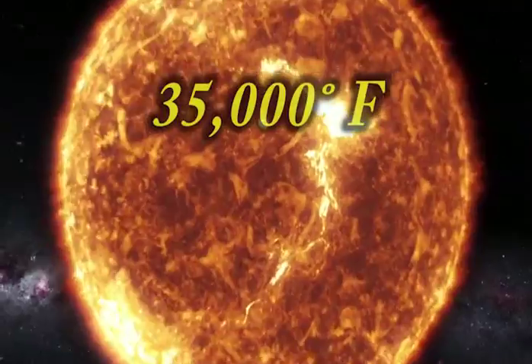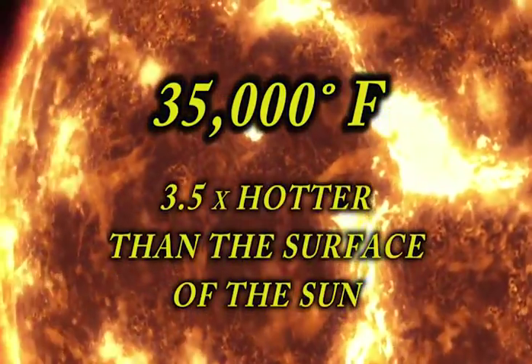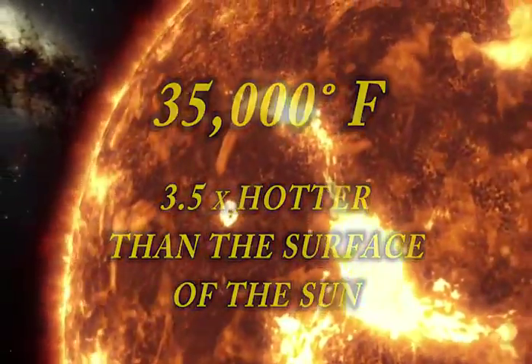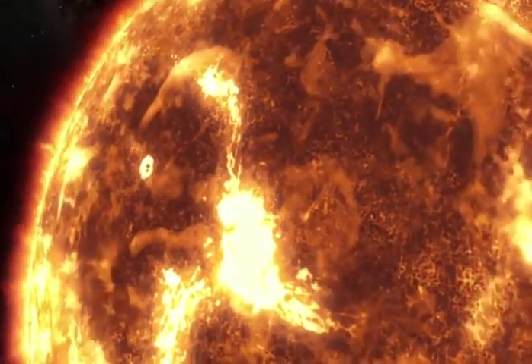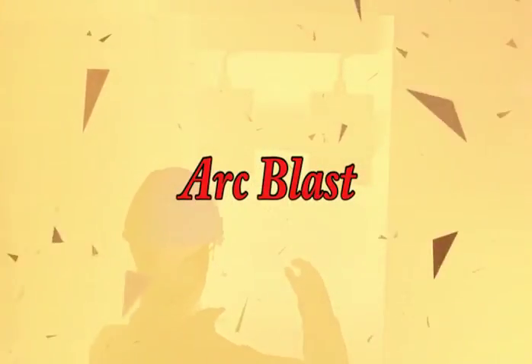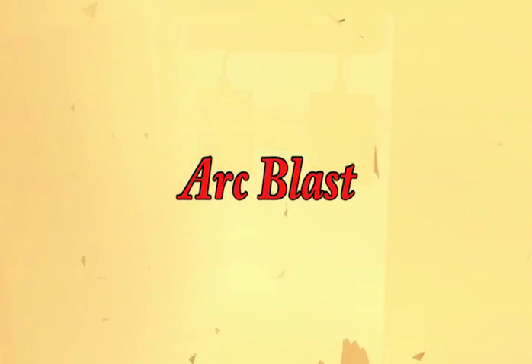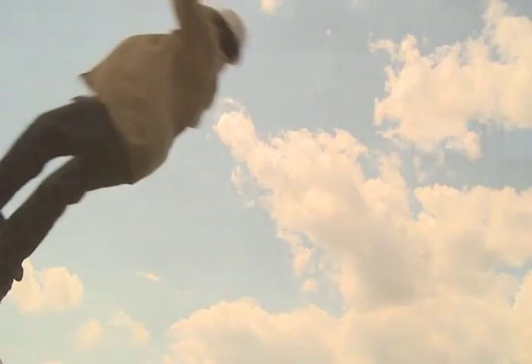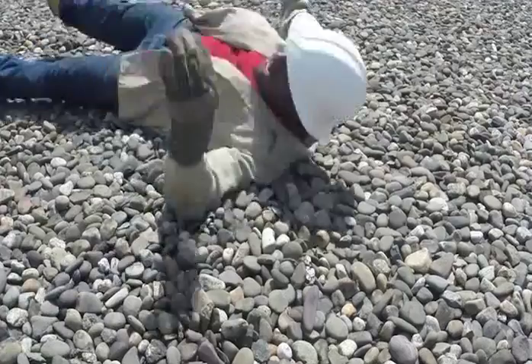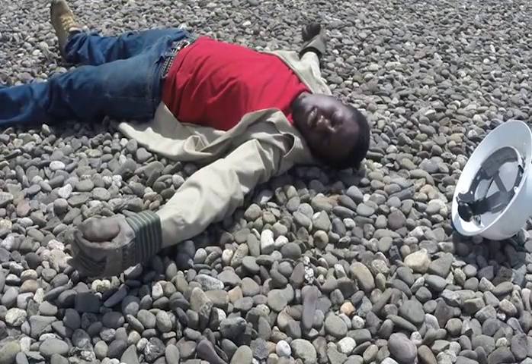Like lightning, these types of arc flashes happen very, very fast, releasing huge amounts of light and heat energy. Temperatures can reach 35,000 degrees Fahrenheit, 3.5 times hotter than the surface of the sun. So an arc flash will instantly superheat the air and can vaporize nearby structures and equipment. Another phenomenon that is often associated with an arc flash is arc blast. Basically, the equipment that is the source of the arc flash explodes. This can throw melted metal and debris outward at nearly the speed of sound. Workers lucky enough to survive a close encounter with an arc blast say it was like standing in front of a shotgun when it's fired.